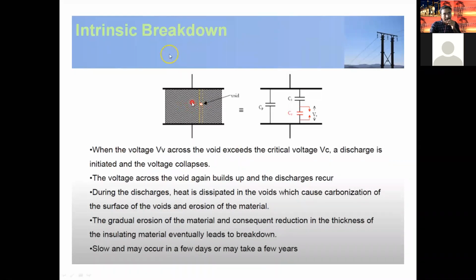If we apply high voltages, the solid type dielectric material can withstand very high voltages, but across the void the air dielectric strength is 31 kilovolts per centimeter, as you know well. So the dielectric strength of the air is very low compared to solid type dielectric materials, which may be around 10 megavolts per centimeter. So we observe a change in dielectric strength.